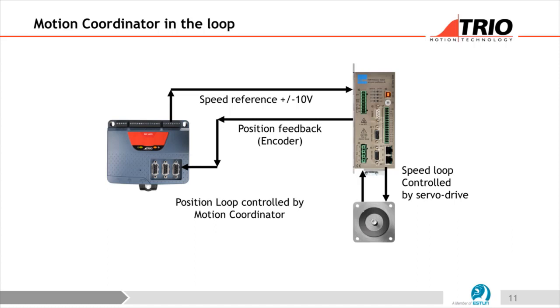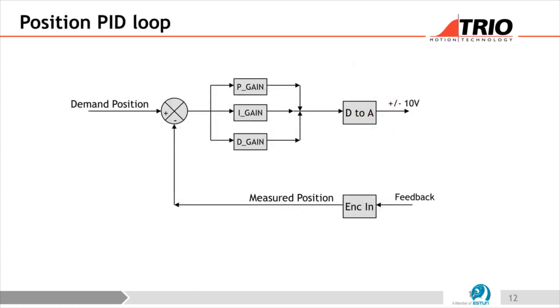Many modern valves and motors have an electronic package on the back, so the drive package might actually be bolted onto the motor. What we're giving out is a speed reference of plus or minus 10 volts, and we're getting position feedback as an encoder simulation — either an encoder or resolver on the back of the motor feeding into the servo drive, which controls the speed loop, commutates the motor, and gives us encoder pulses for motor position.